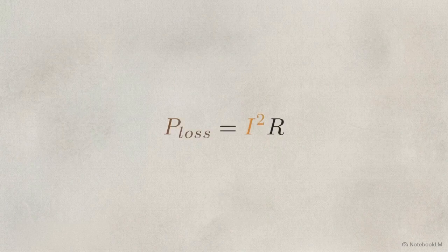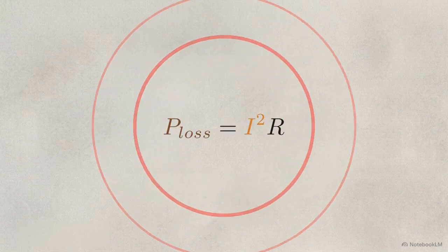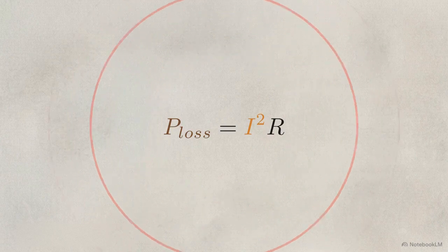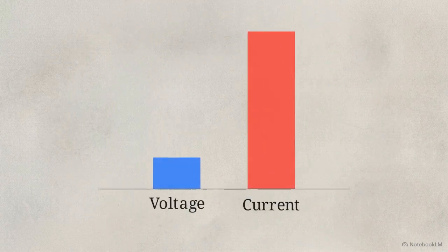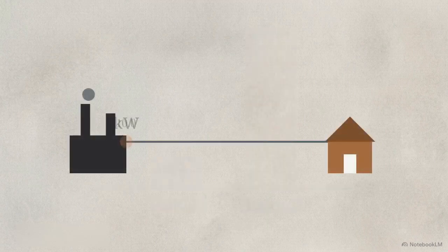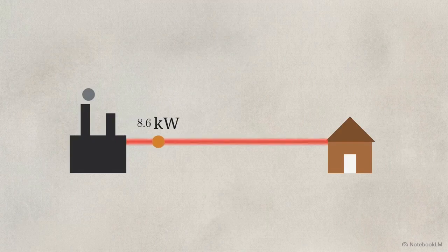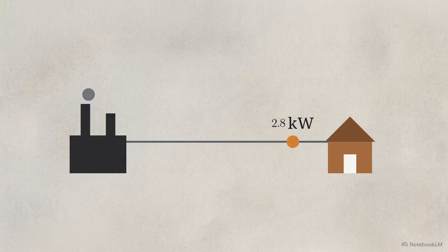The power lost in a conductor equals the square of the current multiplied by the wire's resistance. This lost energy radiates outward as wasted heat. If the voltage is not modified, the current must be high to meet power demands. If a cable has 5 ohms of resistance, attempting to send 10 kilowatts at 240 volts results in an 87% energy loss before the power reaches the destination.